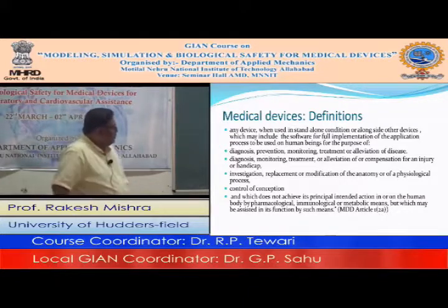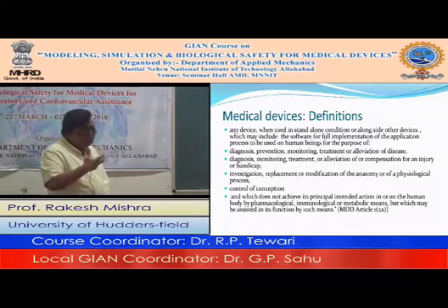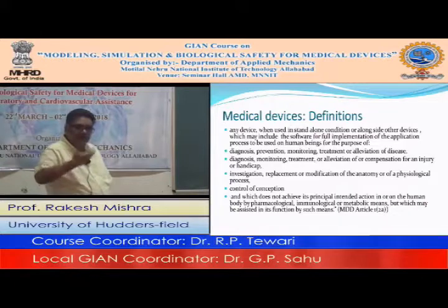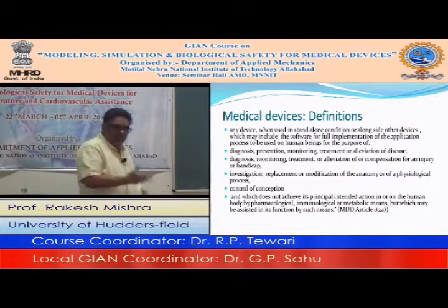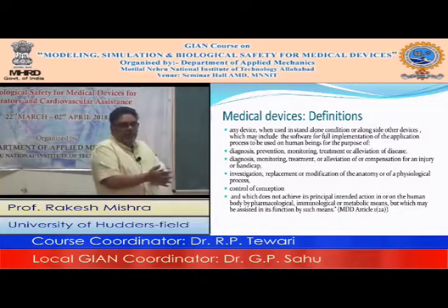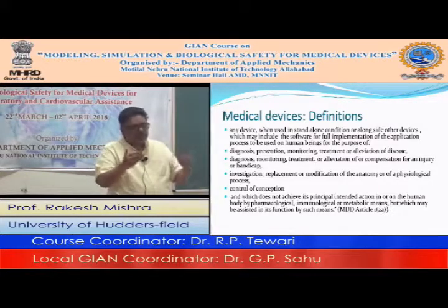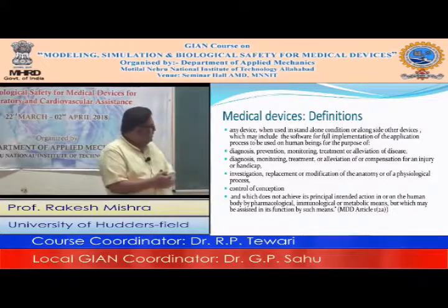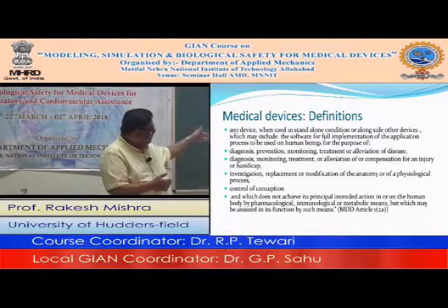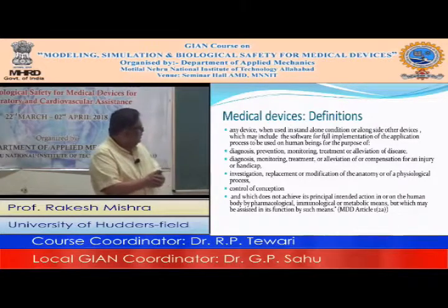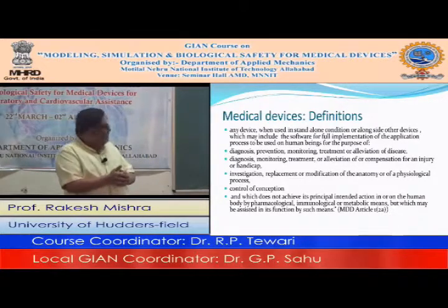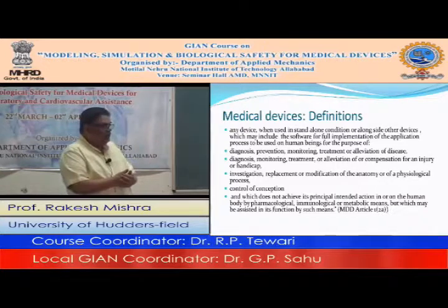For example, if you have a stent, you want to avoid complications, like the body rejecting foreign material, so you can suppress that through medication, but that is not the main aim. A medical device should not achieve its principal intention by pharmacological, immunological, or metabolical means.